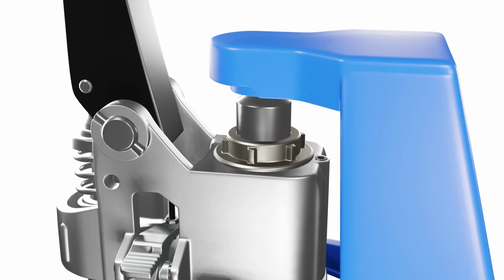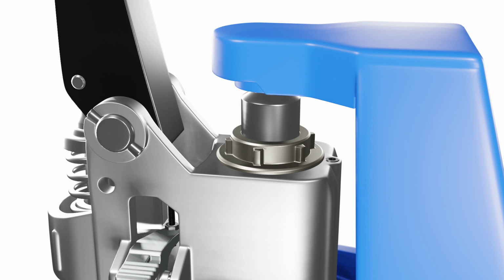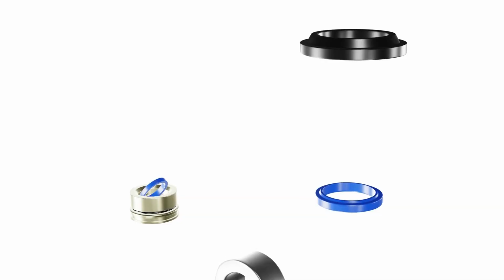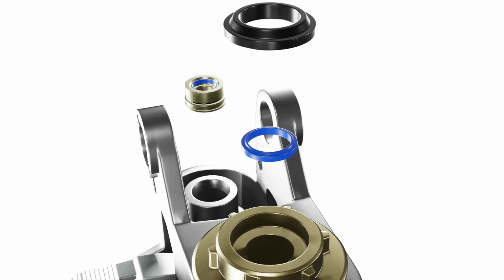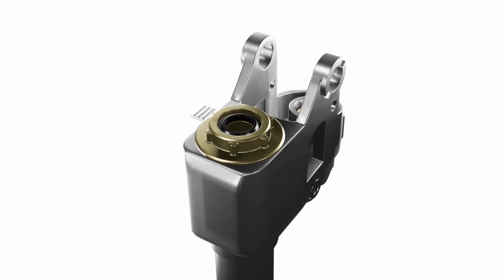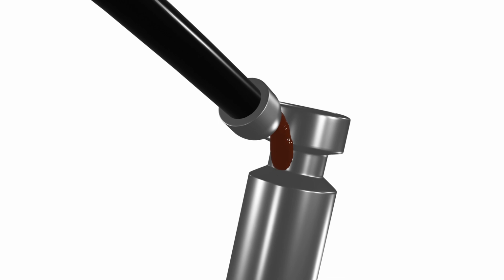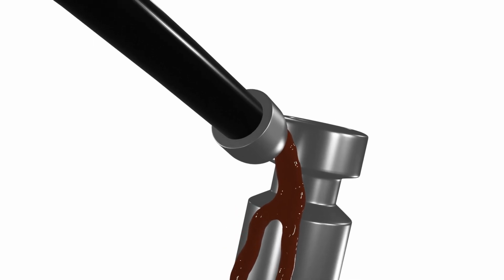Check the hydraulic pump and cylinder for any signs of wear or damage. Contact a professional service technician for repair or replacement if you notice any. Inspect the hydraulic seals for any signs of damage or wear. Replace them if necessary. Grease the pump piston and cylinder rod using the grease gun. This will help prevent corrosion and friction.